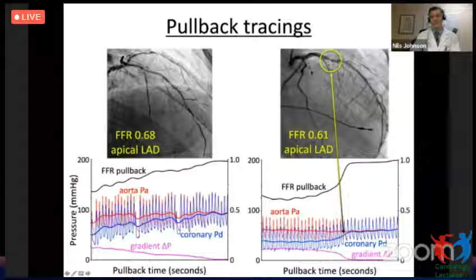But during a pullback measurement, you see that these twins or apparent twins on the surface actually have very different physiologic patterns. On the left-hand side in this LAD, you see as I move the pressure wire back from the distal vessel to the aorta, that there's just a very gradual decrease of the pressure gradient shown down here at the bottom. There's not any one spot where the pressure gradient jumps. It's a good measurement. We get back to almost 1 at the beginning, so there's no important drift. Whereas the case at the right-hand side, while moving the pressure wire back through the vessel, right here at this proximal lesion, boom, there's a sudden jump up almost back to 1.